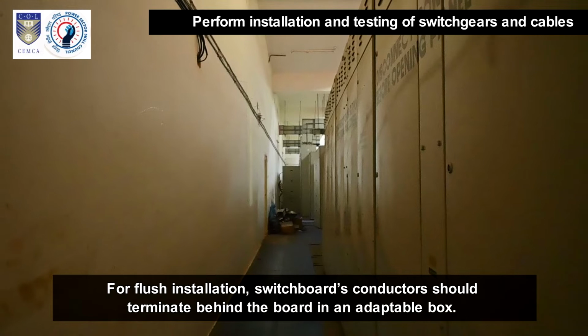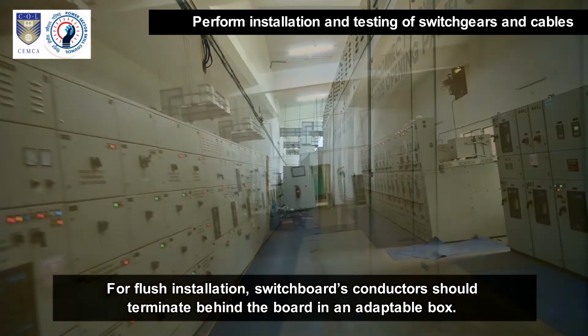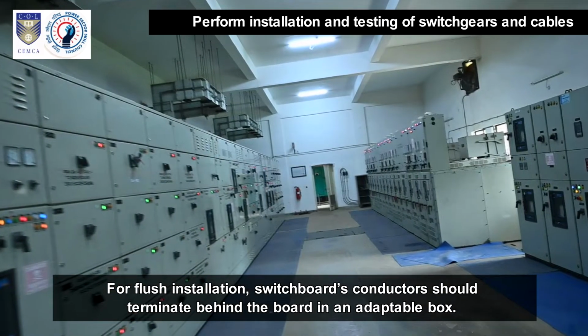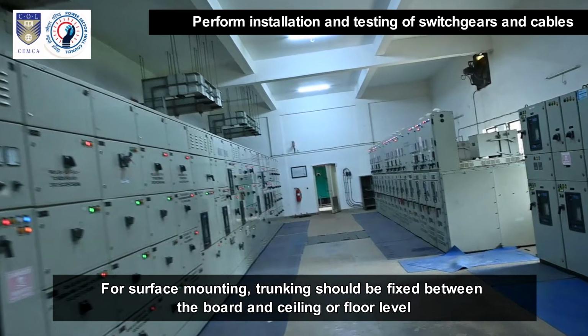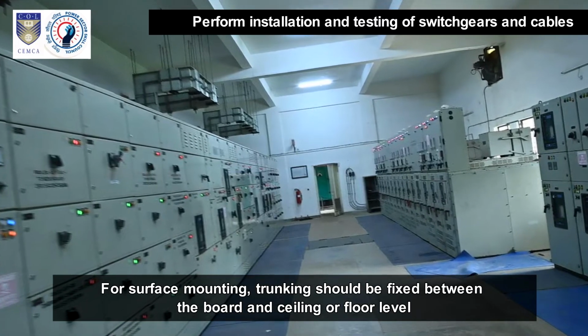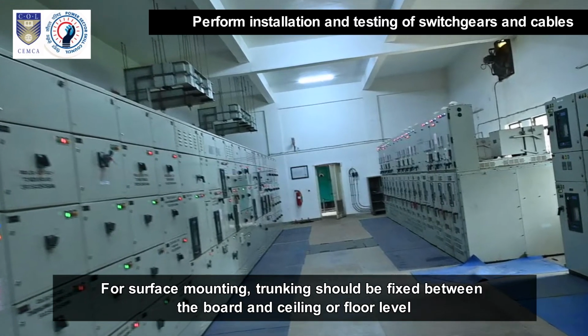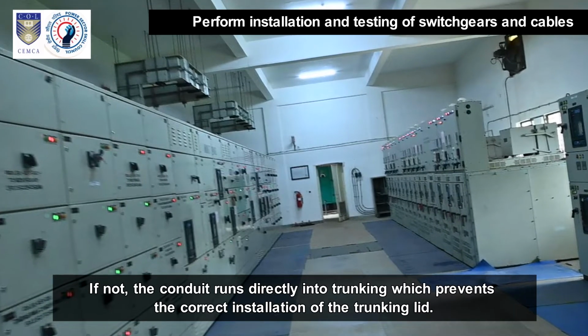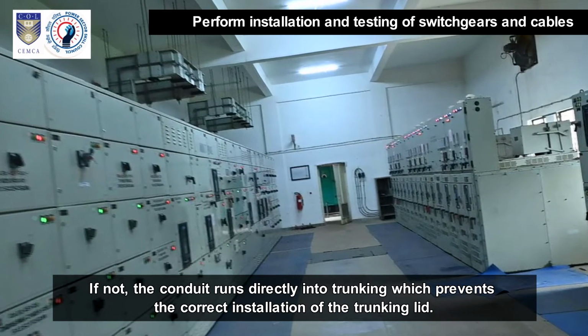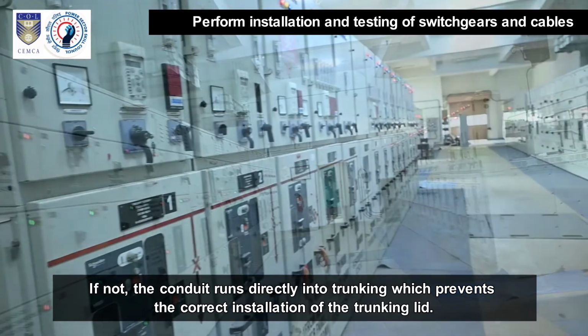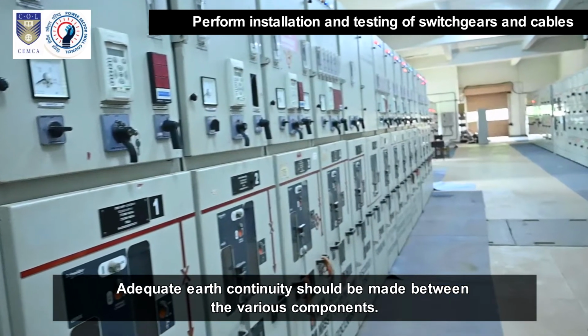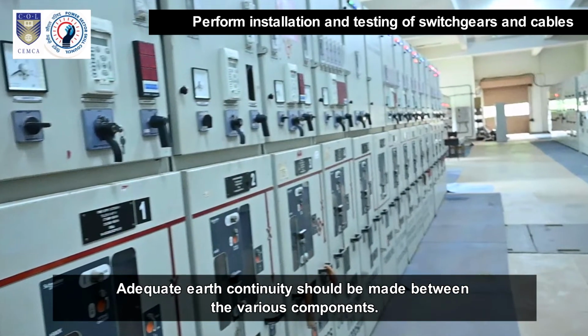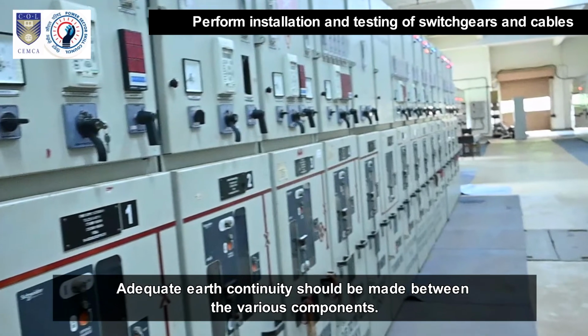For flush installation, switchboard's conductors should terminate behind the board in an adaptable box. For surface mounting, trunking should be fixed between the board and ceiling or floor level. If not, the conduit runs directly into trunking, which prevents the correct installation of the trunking lid. Adequate earth continuity should be made between the various components.